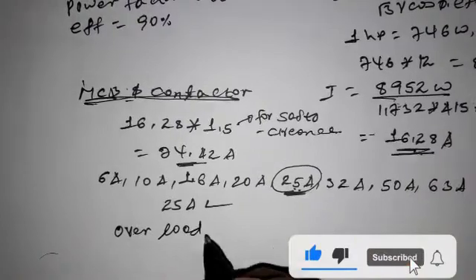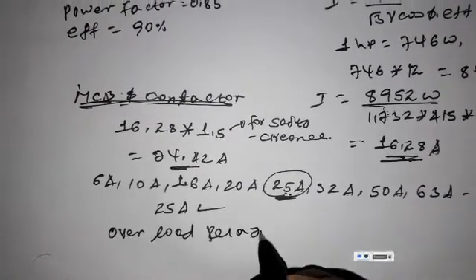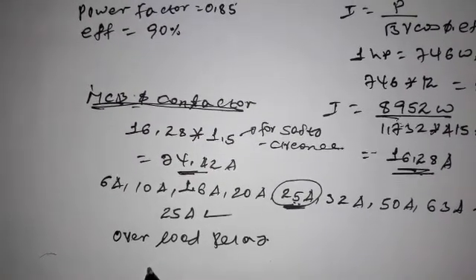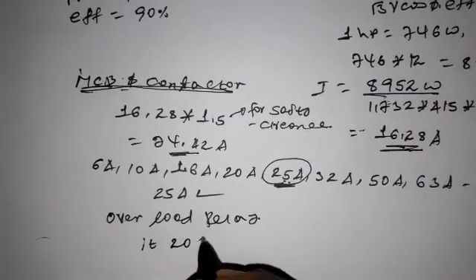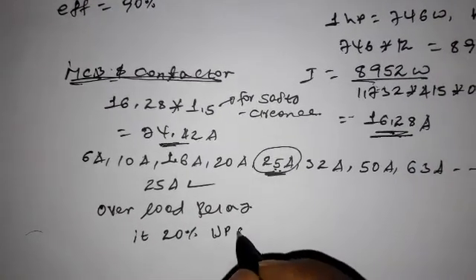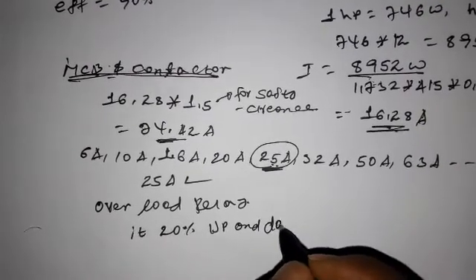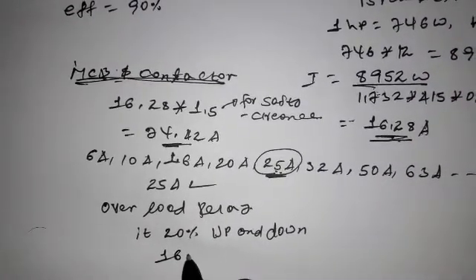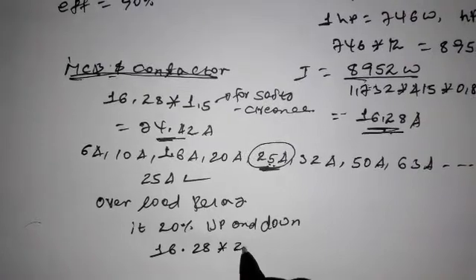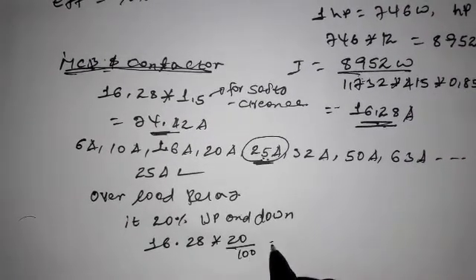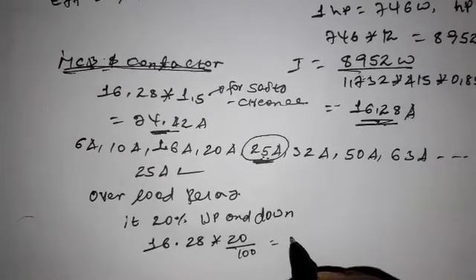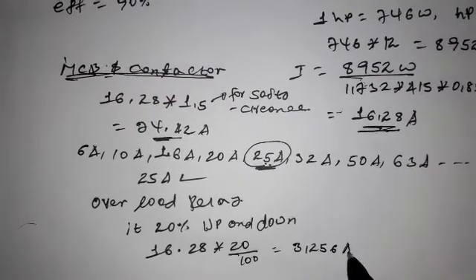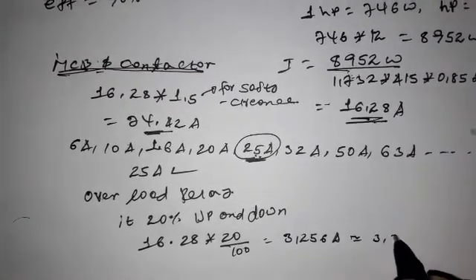Overload relay. 20% up and down. 16.28 times 20 divided by 100 is equal to 3.256 Ampere, approximately 3.3 Ampere.